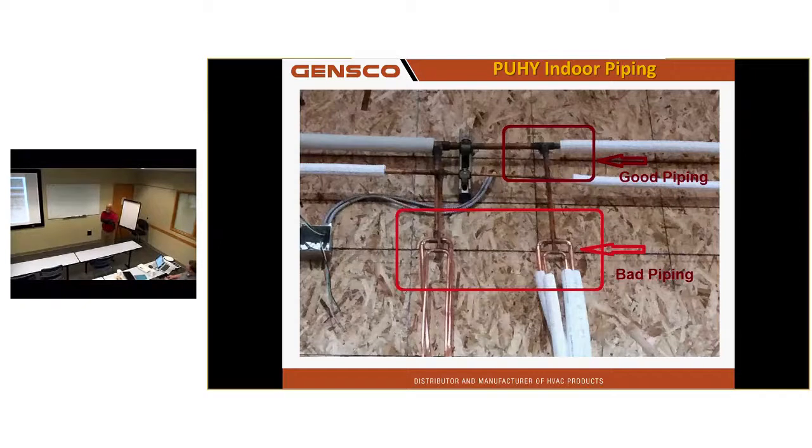You don't realize it's gonna take me 2 weeks to fix all this? With all the fittings and brazing and nitrogen and all that stuff? We would have saved a ton of money. It would have worked perfect, because for every outdoor unit there were 8 indoor units. 1 header, 8 lines going to the 8 indoor units. Again, this is something I'd say, hey, can you repipe that? Even if it's been running for 6 months.